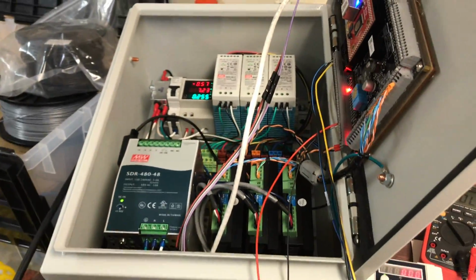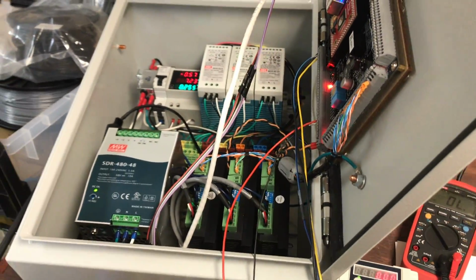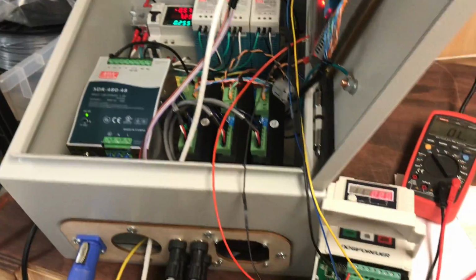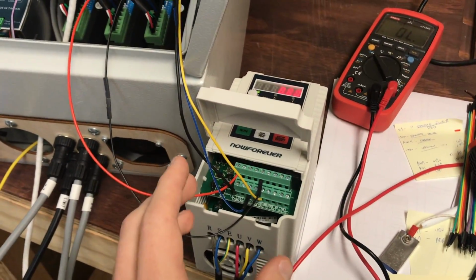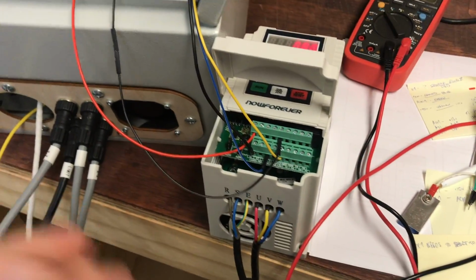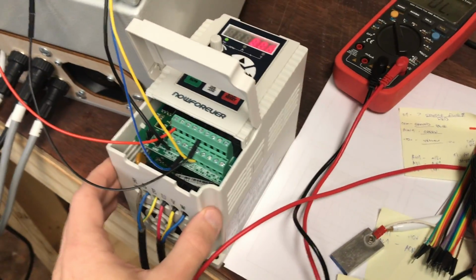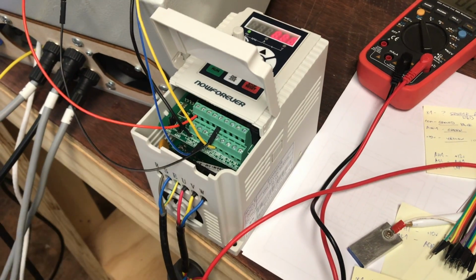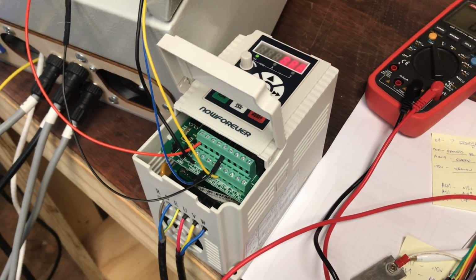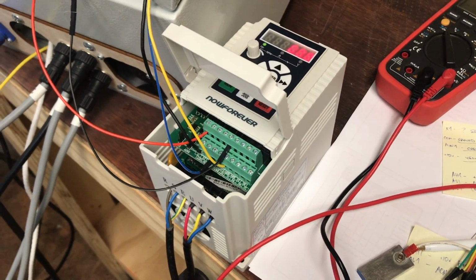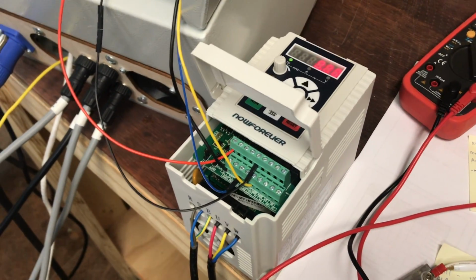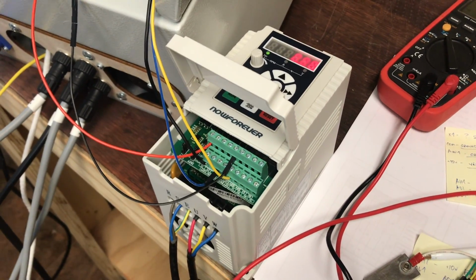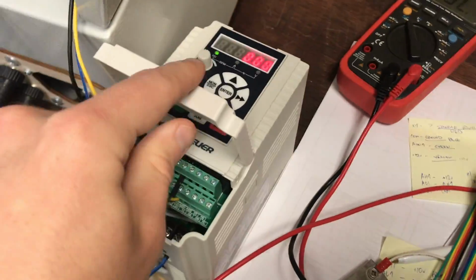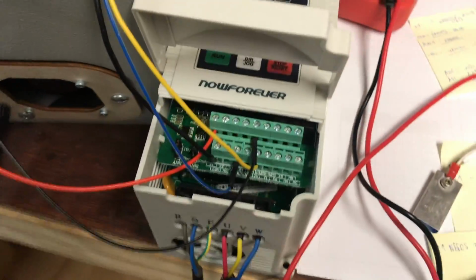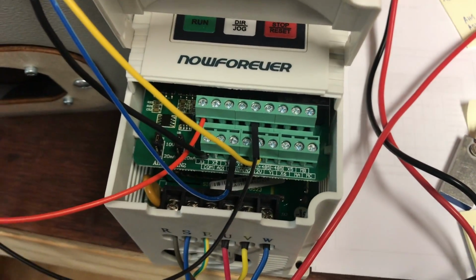The primary goal of this enclosure, before I go on to the little details that I figured out today, was to isolate the VFD from the rest of the electronics. So eventually when the ATC spindle comes in, I'm going to put the VFD in its own enclosure alongside all of the other ancillary components for the spindle, like the solenoid array that I know I'm going to have to put together for the ATC piston controls. But what I want to talk about right now is the analog input for controlling the spindle speed.